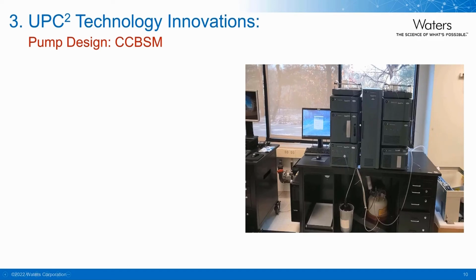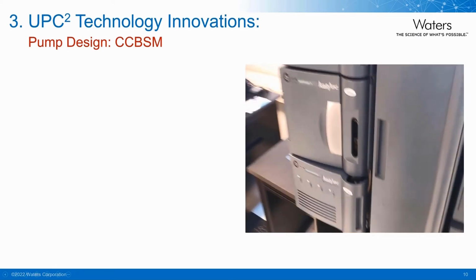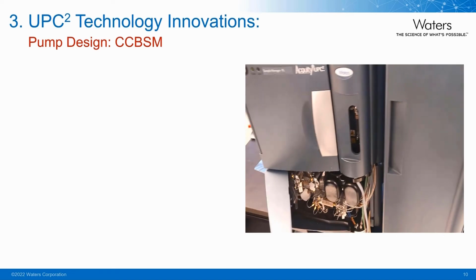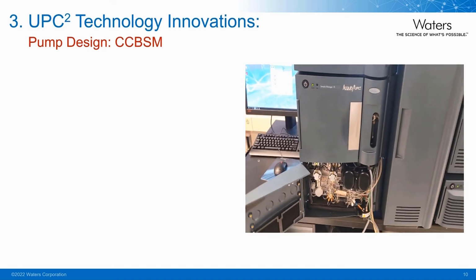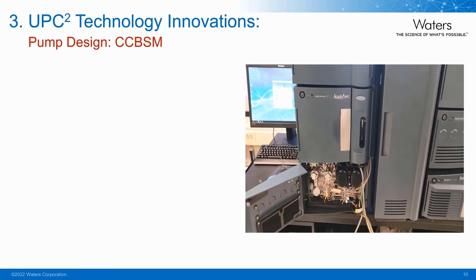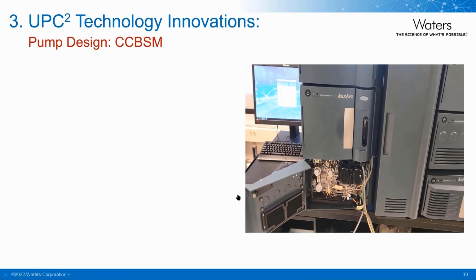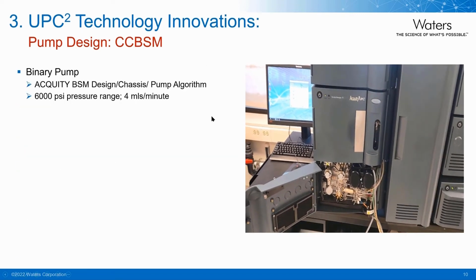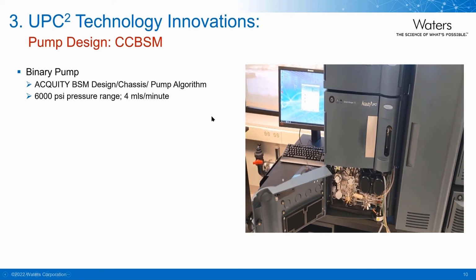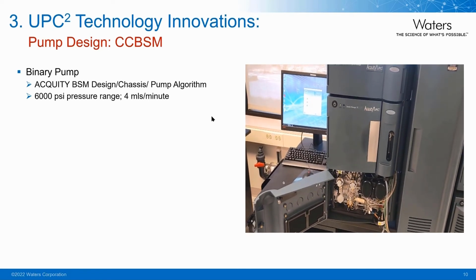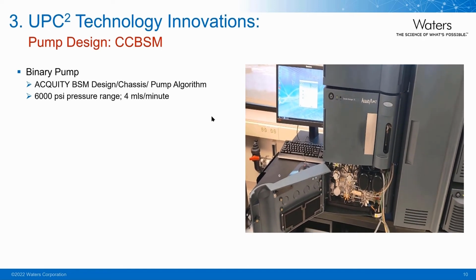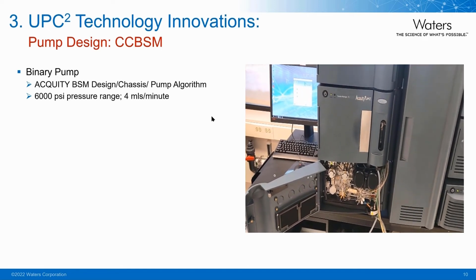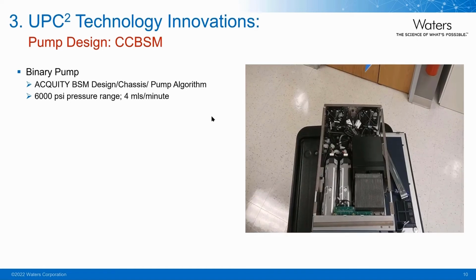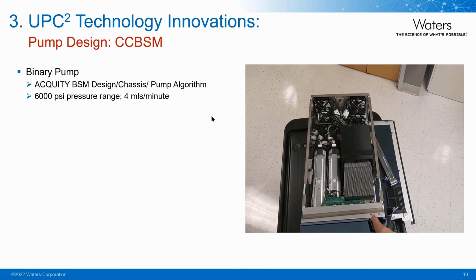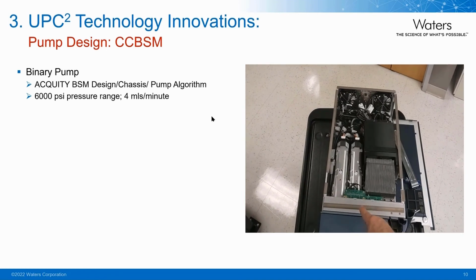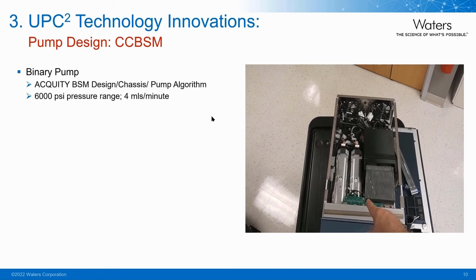One of the major contributions to Analytical SFC is the UPC² pump design, which is called the CCBSM, and I'm showing you right here. So one of the major functions is that it's a binary pump, but it uses the same ACQUITY BSM design as UPLC and same chassis, but also same pump algorithm, which reduces the background noise because of pump pulsations. It's 6,000 psi, 4 mils a minute.